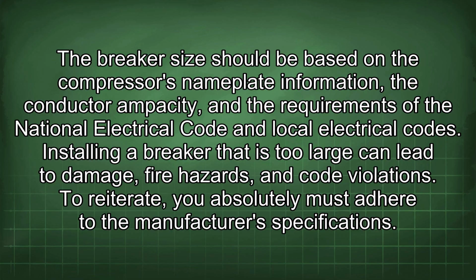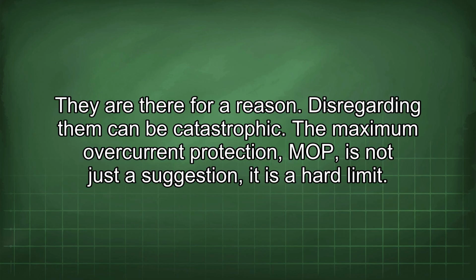Installing a breaker that is too large can lead to damage, fire hazards, and code violations. To reiterate, you absolutely must adhere to the manufacturer's specifications. They are there for a reason. Disregarding them can be catastrophic. The maximum overcurrent protection, MOP, is not just a suggestion, it is a hard limit.